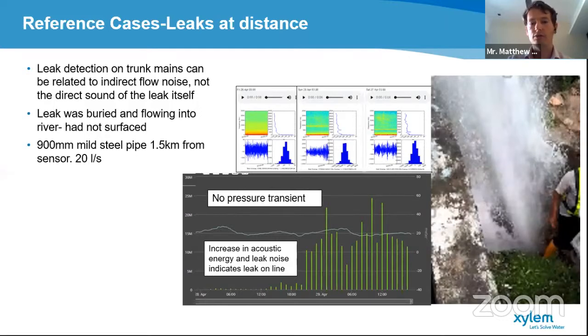So it was important using this sensor to be able to pick it up at both an unusually large distance and with a buried leak that did not surface. This is because we were able to pick up the sound of the flow within the pipe as a result of the leak.